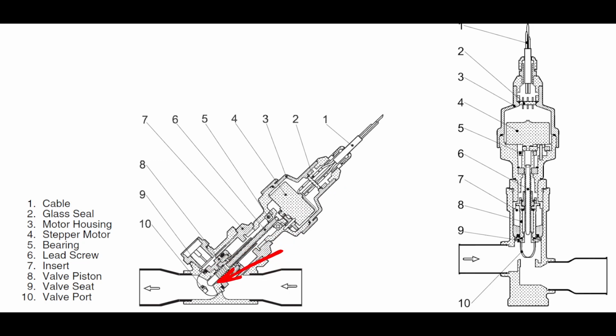It's hit the dead stop of the valve body, and whether it be the threads or the clutch mechanism they have, whatever the case may be, the motor is still rotating where it's trying to, but it's skipping because it can't close any further. It has mechanically come to a stop. Now on the open, or the next steps, the first step is fully close. The second step is go to an open. So then it will initiate an open procedure. It will try to drive the valve to a fully open state. And you want to hear that dead head, or that stop point.